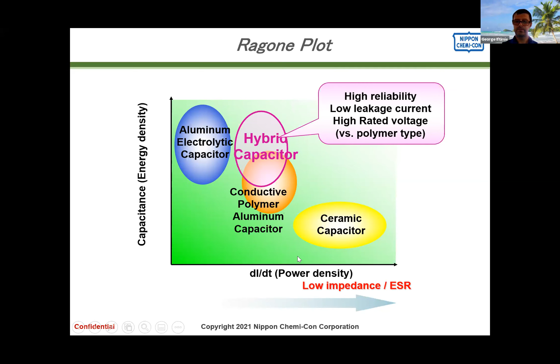A little bit on the voltage. Hybrids are usually available up to 80 volts. Some competitors have higher voltage than that. We found that we're working on a 100 volt rated voltage polymer, but humidity resistance is much lower for above 80 volts than it is for 80 volts and below. And then there's some points of ESR and so on.